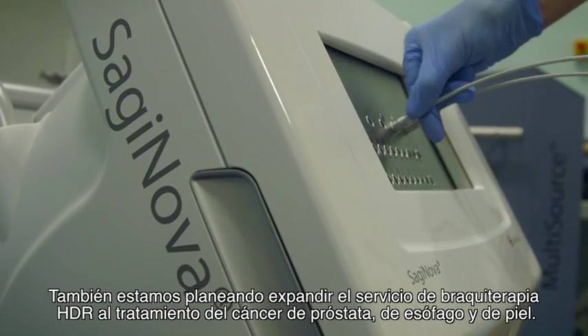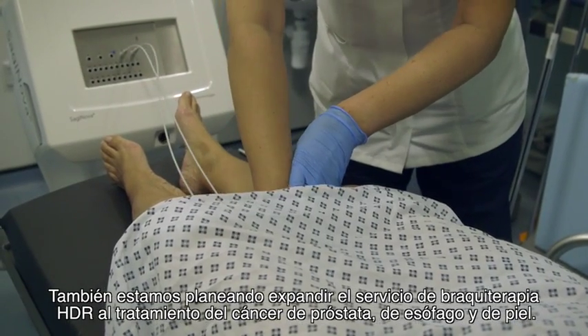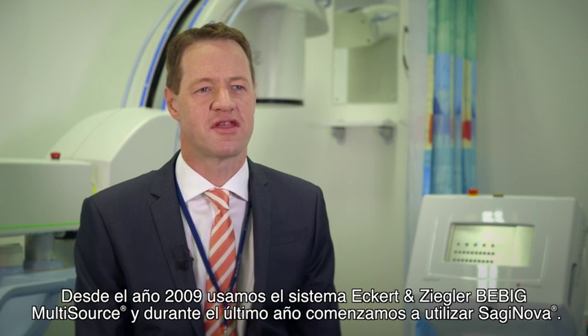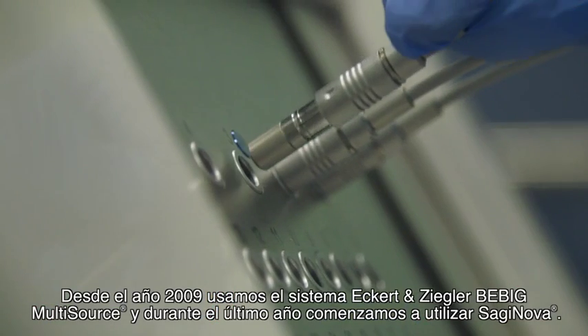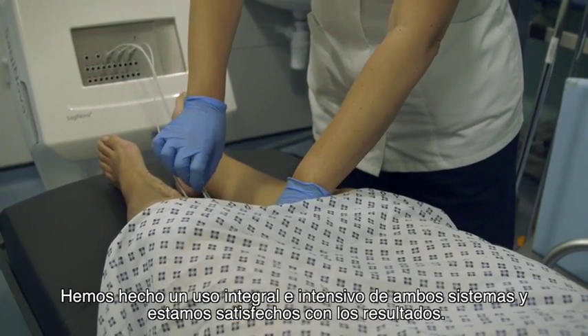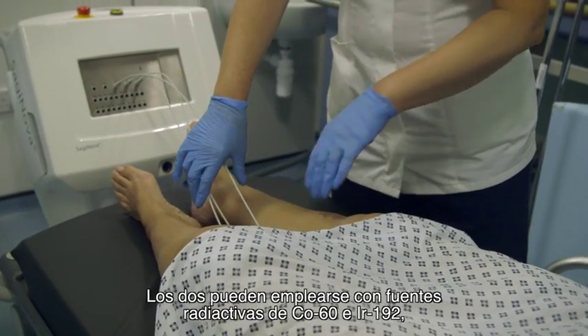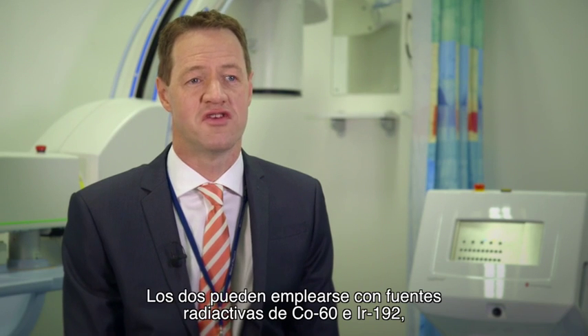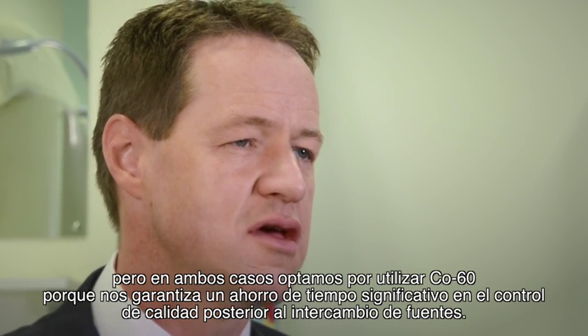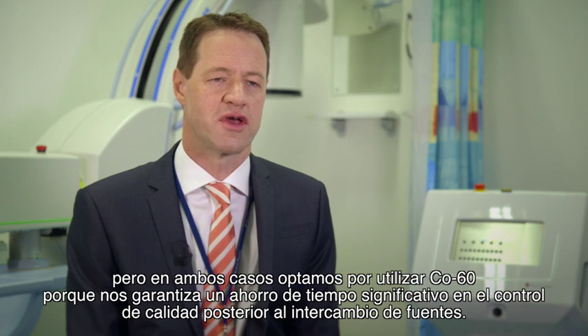There are also plans in place to expand the HDR brachytherapy service to prostate cancers, esophageal cancer and skin cancers. We have been using the Eckert & Ziegler BEBIG MultiSource since 2009 and for the last year have been using the Saginova system. We have performed comprehensive extensive commissioning on both systems and were happy with the results. Both systems are available with Cobalt-60 and Iridium-192 sources, and in both cases we decided to use Cobalt-60 due to the significant time saving of quality assurance following source exchanges.